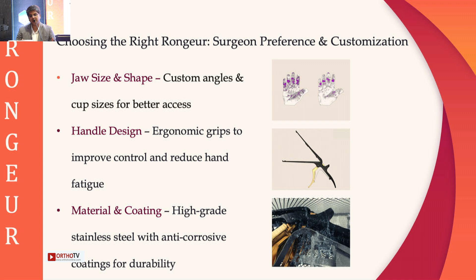So rongeurs, I'll quickly rush through it. He's made my work simpler. So the Kerrison, pituitary, and Leksell rongeurs: these three things are important to be in your spine set, whether you're doing open, regular, whatever it is. You should choose what jaw or cup size you want. And it's always better to have a double action than a single action, because the force, the torque you set in, is less with double-handed. And of course, buy an instrument with ceramic coating. One, because of the anti-corrosive property. And when you put the microscope in the field, whatever reflection comes is absorbed by the ceramic. So ceramic ones are better.